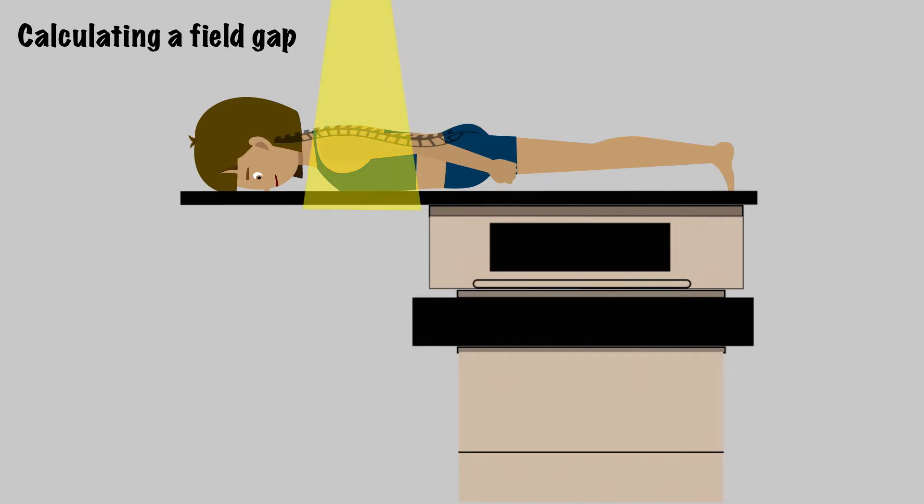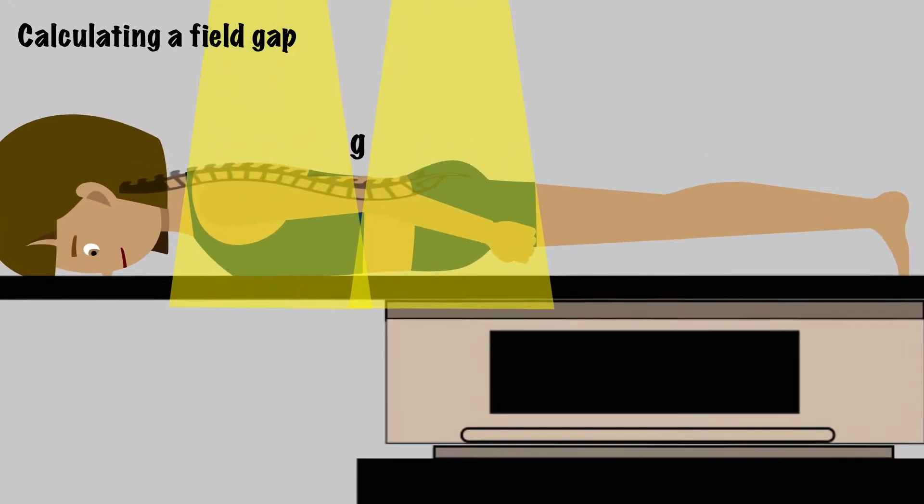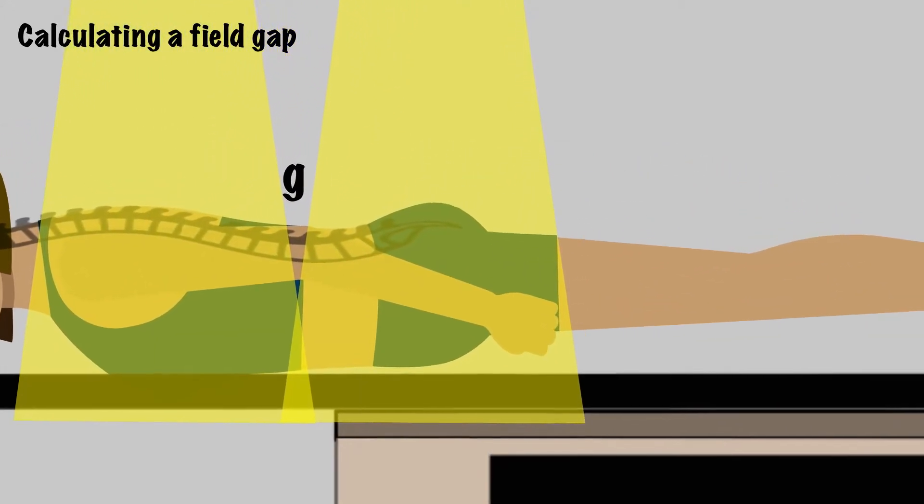We start with the first field, and then the second field. There's a gap at the skin, a match point, and an overlap area of the beams as they exit the patient. Say we want to match at some depth, D. The patient is set up at some source to skin distance, SSD1, with a field size we'll call FS. There's a gap between the fields called G. What we want to do is find the gap given the known parameters.